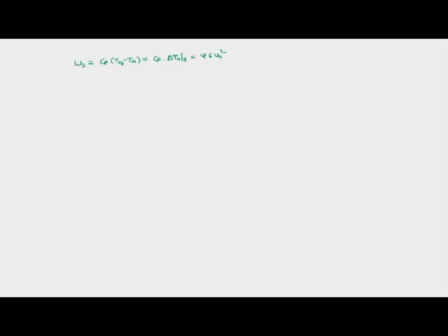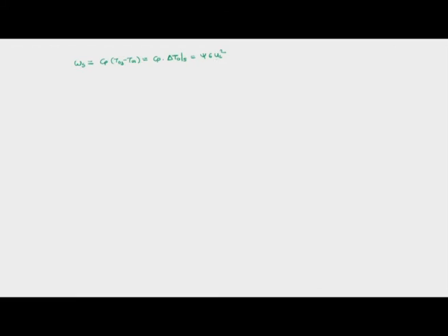We have to keep in mind that this psi sigma U2 square is a specific number corresponding to radial vanes. Psi is a factor corresponding to friction, and sigma is a factor corresponding to inertia. Considering these two factors, we have found psi sigma U2 square for the actual stage work. So delta T0 in a stage is equal to psi sigma U2 square upon Cp.